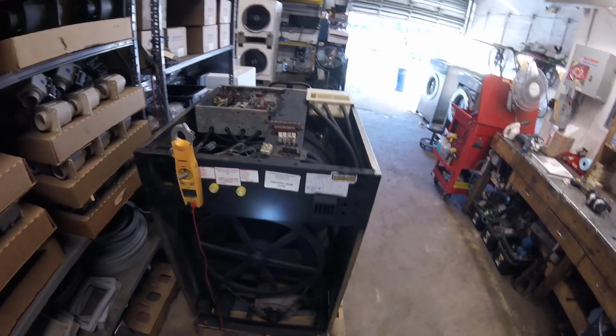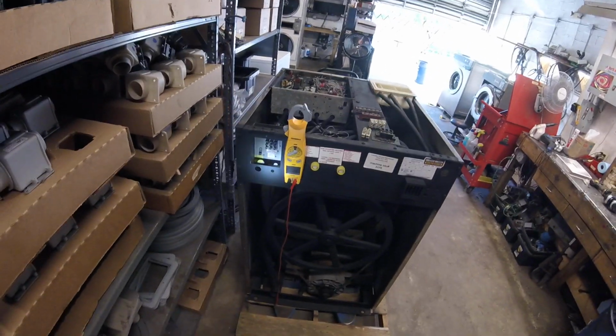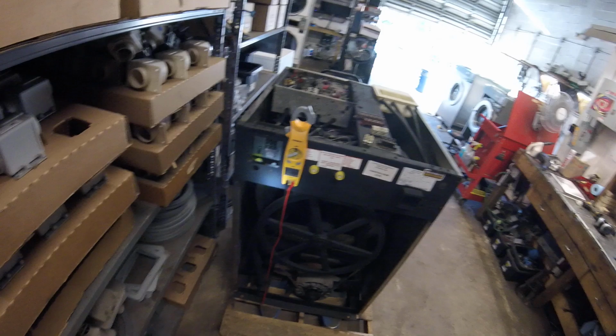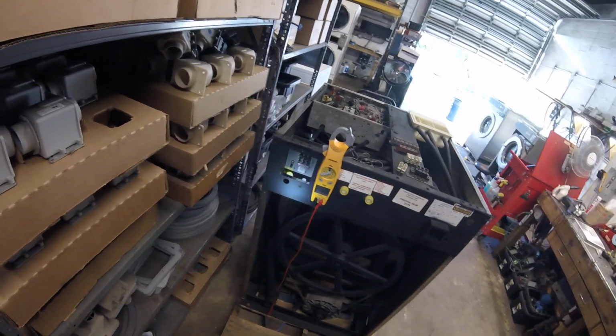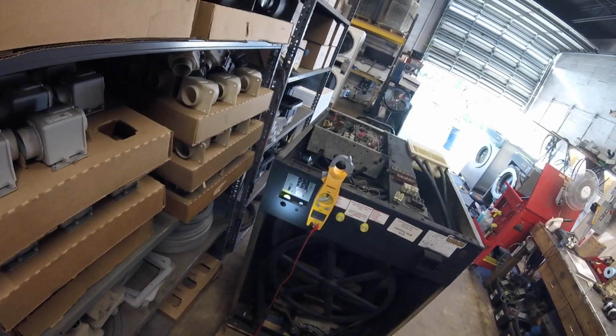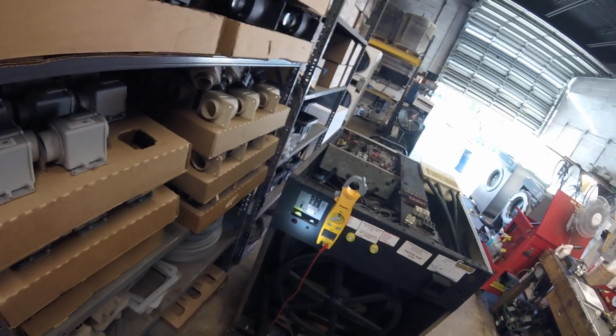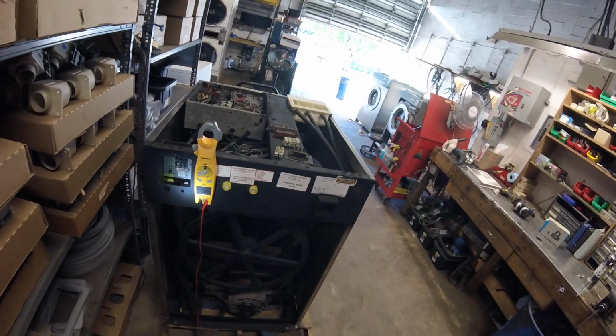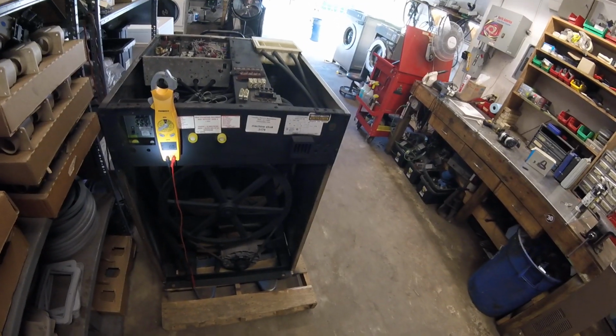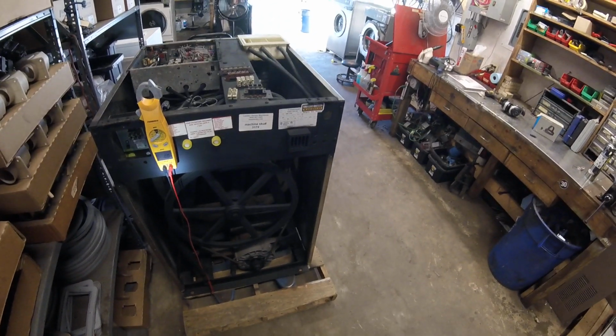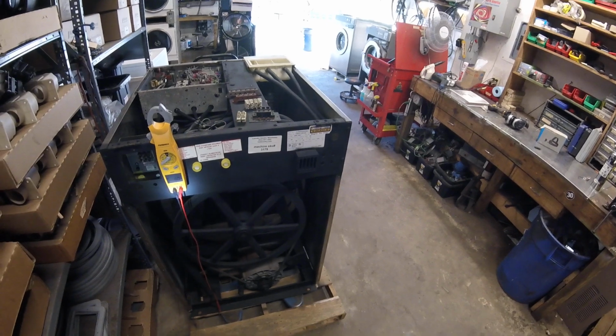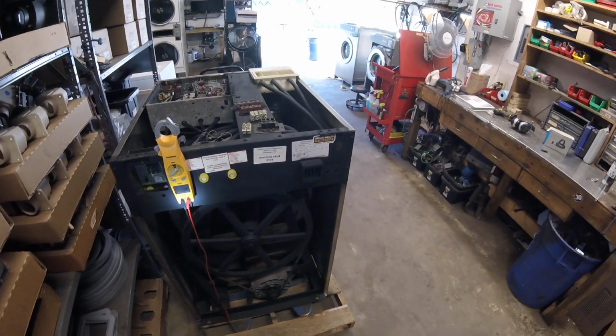Now, when you're reading voltages for the 110 volt stuff, anywhere from 110 to like 124 is acceptable. Anything over or under that, you're going to want to look into the problem. You shouldn't be reading under or over that. Same with 200, you should be 208 to 240. It's important on those machines, if you have transformers, to check them. Some of them have separate legs for 208 or 240, depending on what you're getting for voltage.